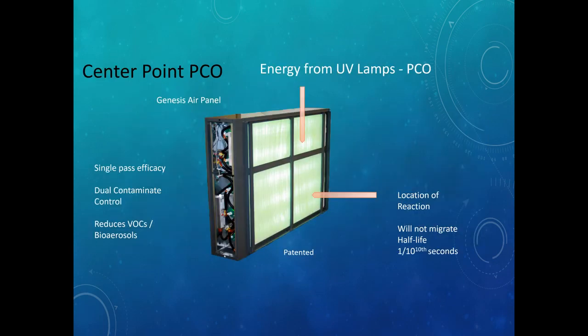Here's how the panel itself is distinctive. There are a number of PCO products on the market. Most have a honeycomb structure, and some require downstream carbon because they create intermediaries with UVC. One reason we did third-party testing using a typical office mix formulated at Lawrence Berkeley is that we don't create secondary or daughter intermediaries at any concerning rate. That testing is available through Trane.